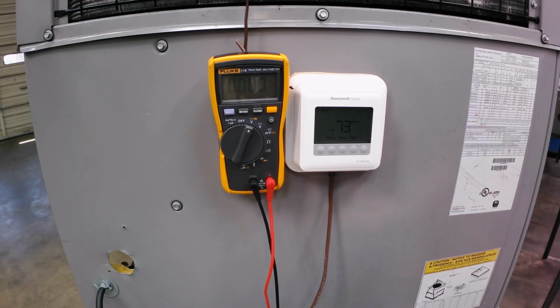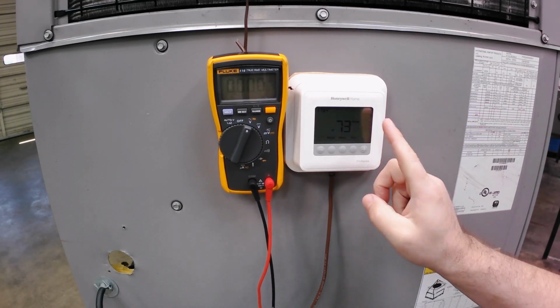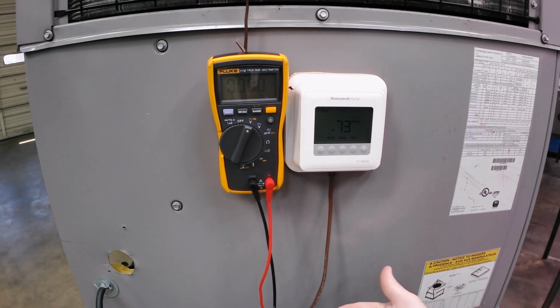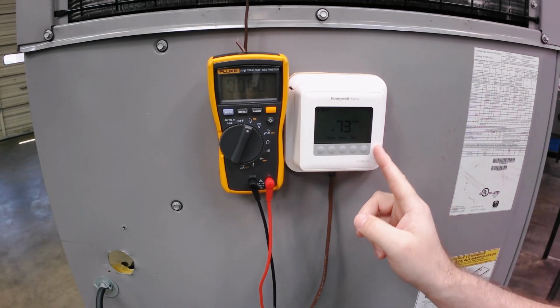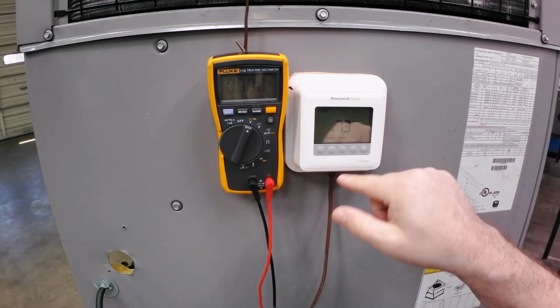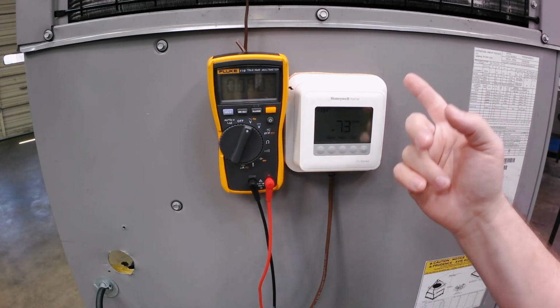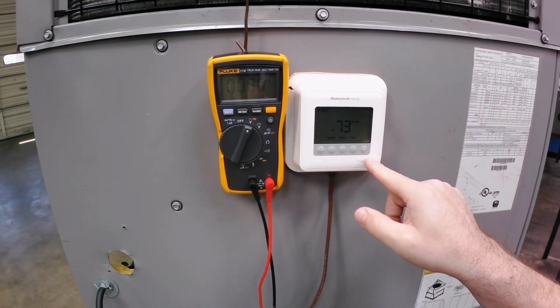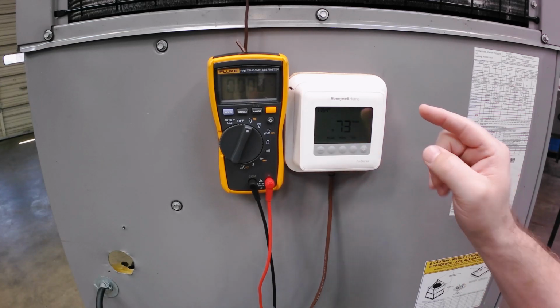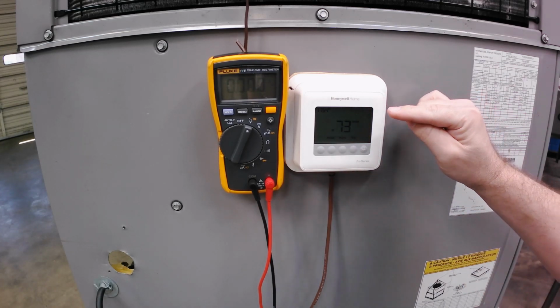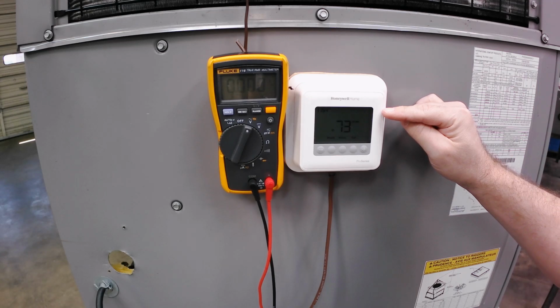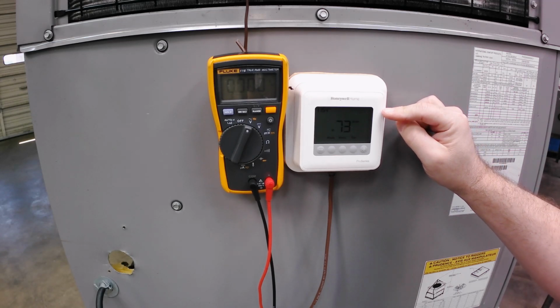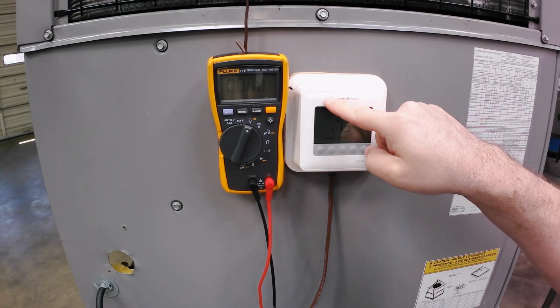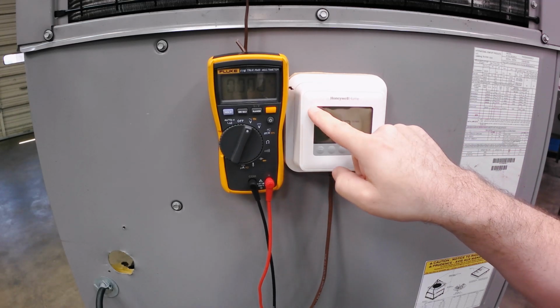Okay, that was a little weird. I don't know what happened there, but as long as I've got power, I know what I can expect now. What I can do is turn the system on, for example, for the fan or the compressor, or I can turn the heat strips on. And what should happen is the R should go across whatever switch you just told to close. R goes across the switch and comes out G. That is a power output.